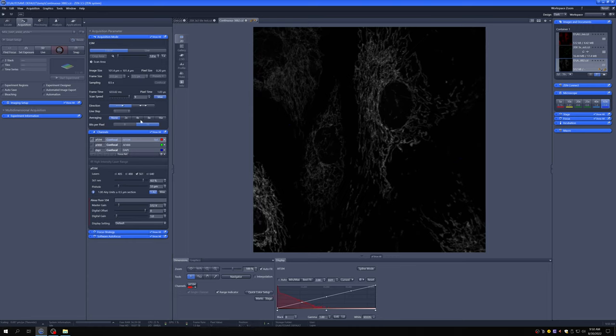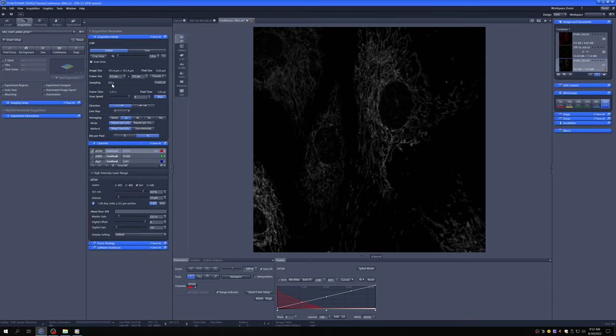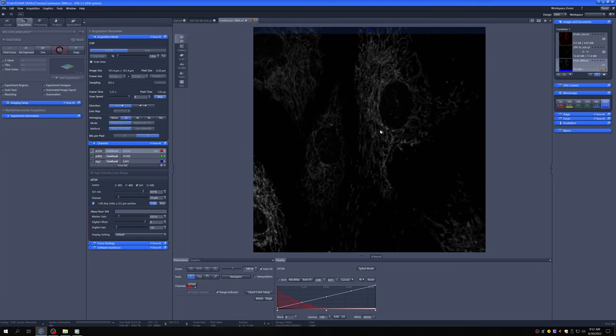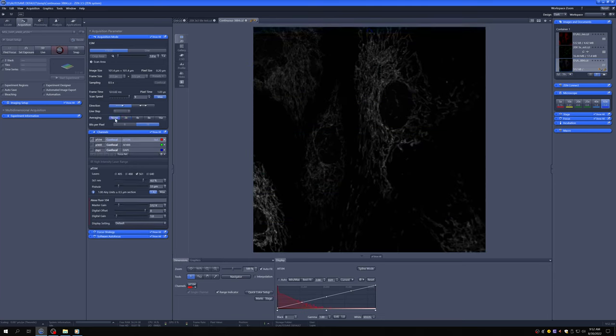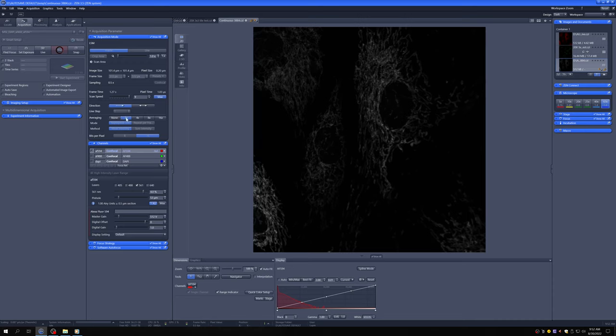One of the things we can do is averaging. What averaging will do is instead of going to each location once in the sweeping of the laser, it goes to each location however many times it says here. If we do 2x averaging, the frame time is now double what it was before. If we go to continuous, we can see whether that had any effect. There's a slight improvement in quality when you go to 2x, but it's really not very dramatic. If you don't really see much of an effect of averaging, there's really no point in doing it because it'll just cost you time.